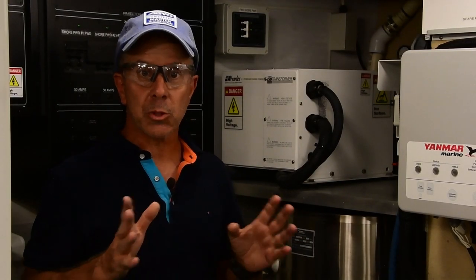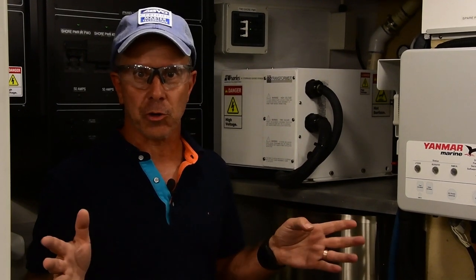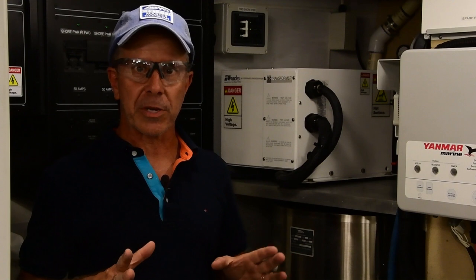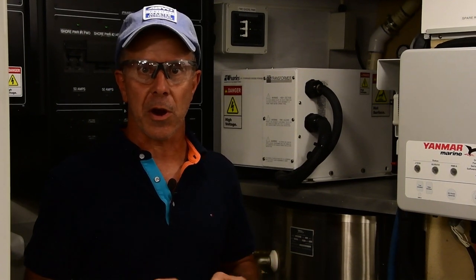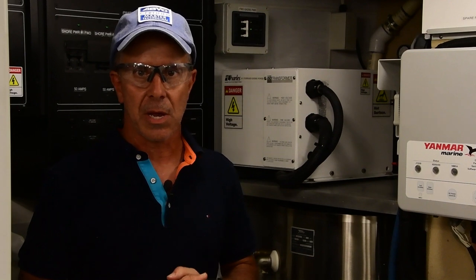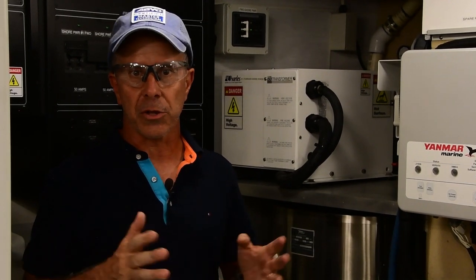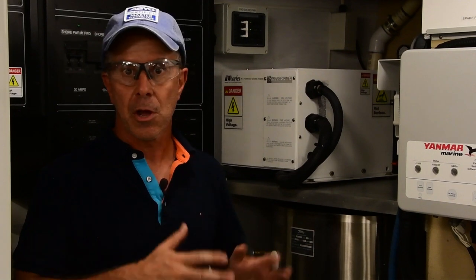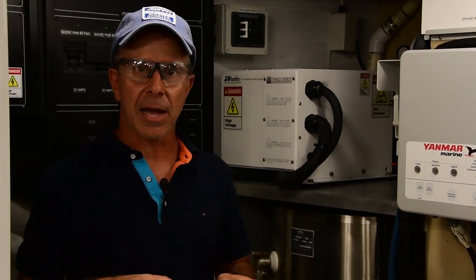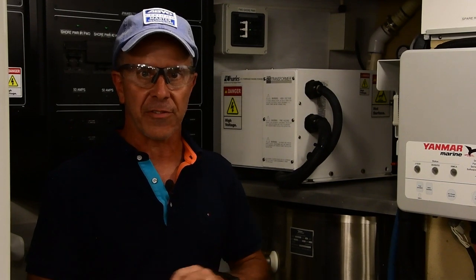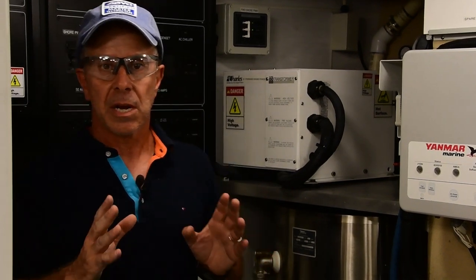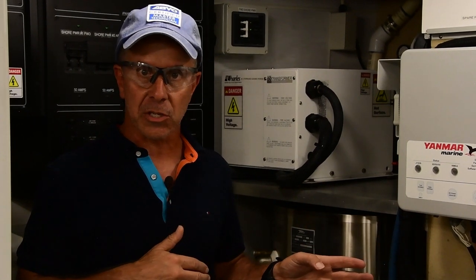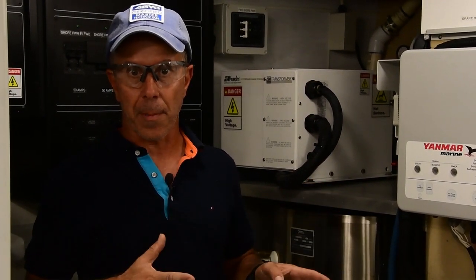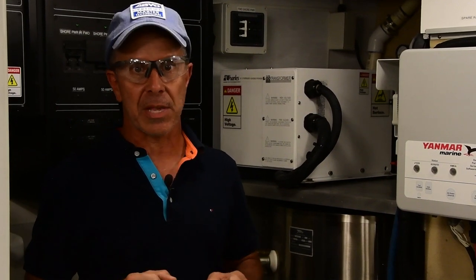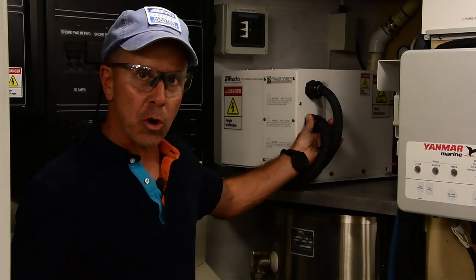Now, it goes without saying that transformers are electrical pieces of equipment, and therefore they must be installed properly and fully in accordance with American Boat and Yacht Council guidelines. There's a chapter in ABYC called E11 that covers transformer installations, both polarization and isolation, and guides installers how to wire them properly and safely. Critically important that those guidelines be followed, as well as the installation instructions provided by the transformer manufacturer. Now, one of the key components in that installation, and one that is frequently violated, is the utilization of what's called a cord grip.